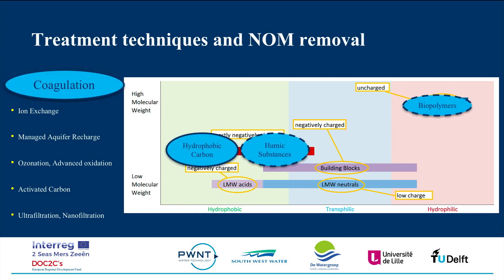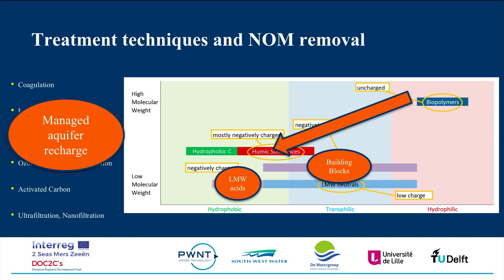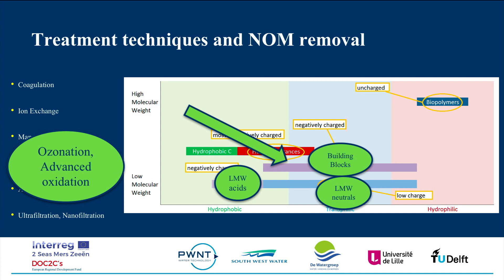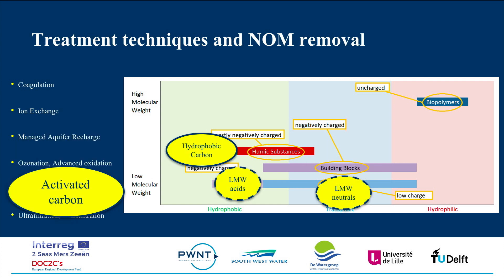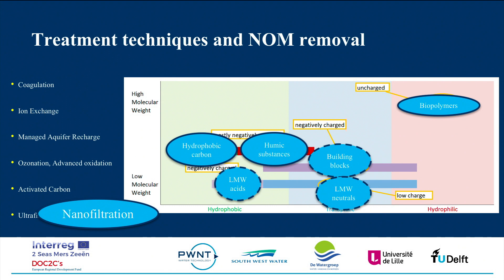Coagulation removes hydrophobic carbon and partially humic acid and biopolymers. Ion exchange removes charged particles that are smaller than the fraction targeted by coagulation. Biological mechanisms in managed aquifer recharge change larger hydrophilic NOM fractions to smaller, more hydrophobic NOM. During ozonation and advanced oxidation, NOM becomes smaller and less hydrophobic. Activated carbon absorbs hydrophobic NOM and, when there is biological activity, removes smaller biodegradable NOM. The NOM removed by membrane filtration is dependent on its pore size: ultra-filtration removes the larger NOM, while nano-filtration can partially remove smaller fractions as well.